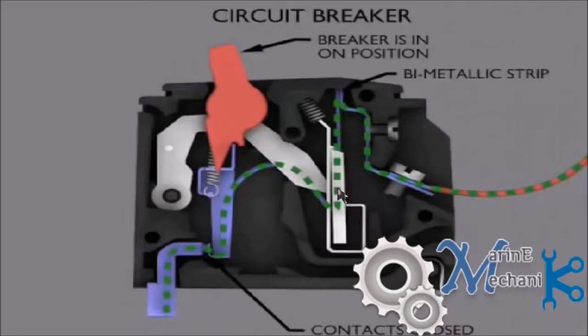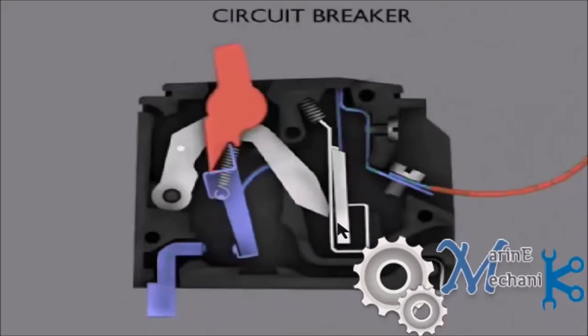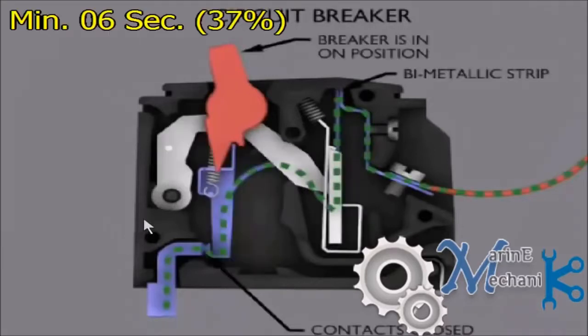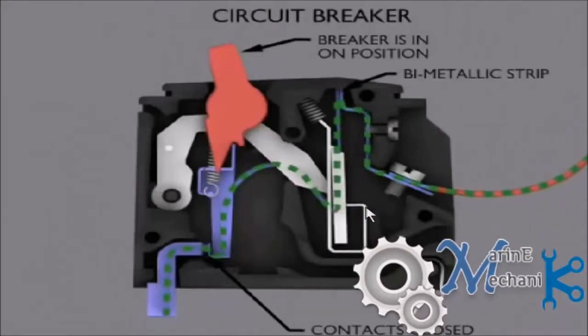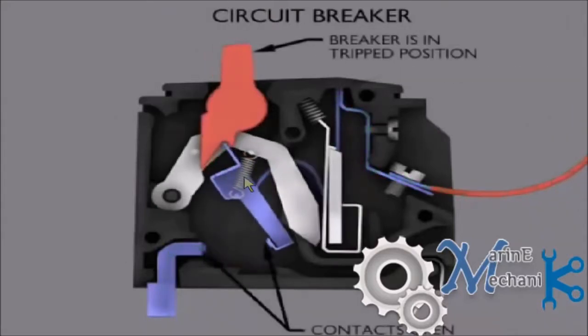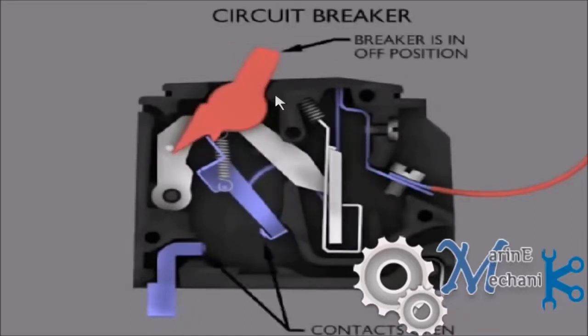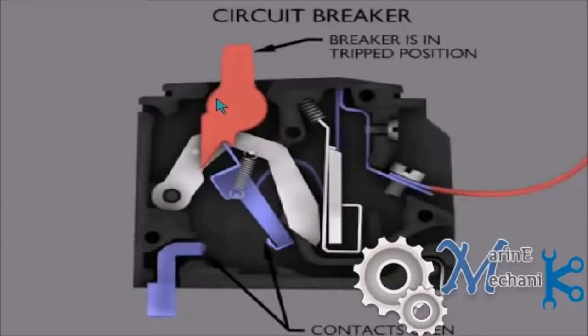So the current flows, it starts to expand, and as it expands, if it's above the limit, this slides down, thus releasing this link, and then the link is open due to the spring. The spring pulls it back. Let's watch it once again. You can see it's coming back, this link is released, and thus this is being pulled back and the contacts are open now. Now the breaker is in trip position.